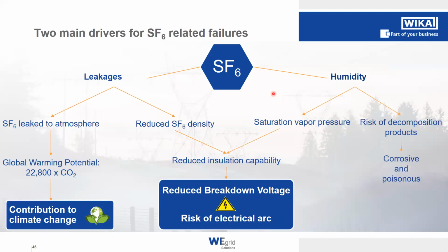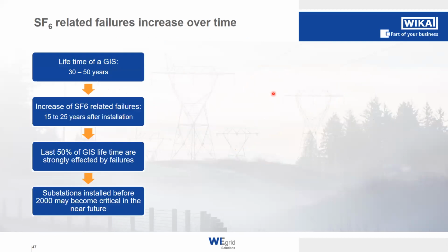On the other hand, with humidity, if there's too much water inside the SF6 gas in your switchgear, the vapor pressure can saturate, and that means there's too much water, and this also can cause a reduction in insulation capability, and therefore a risk of an electrical arc. And which Florian also mentioned, if there is an arc or simply a switching operation, SF6 gas is decomposed into different molecules, and they might recombine with the water in the gas. This can cause corrosive and poisonous products, which can be a danger to the equipment and to the personnel.